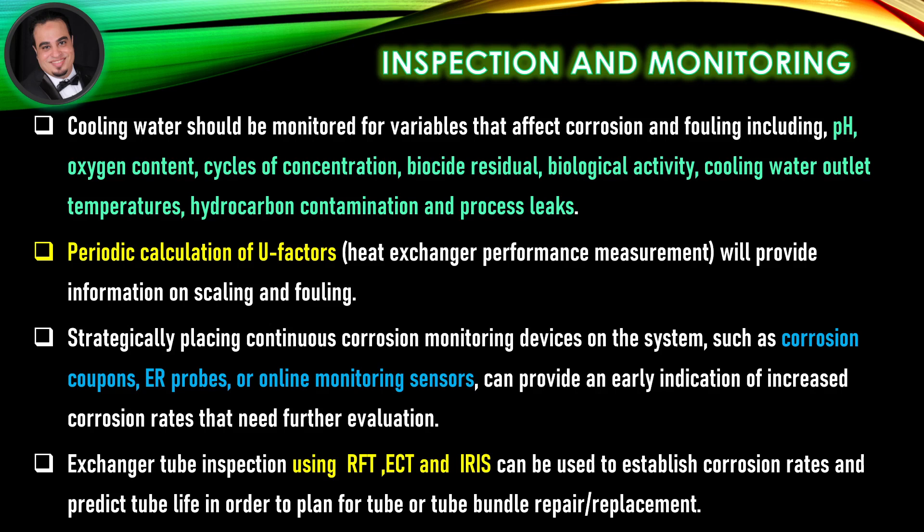Strategically placing continuous corrosion monitoring devices on the system — such as corrosion coupons, ER probes, or online monitoring sensors — can provide an early indication of increased corrosion rates that need further evaluation. Exchanger tube inspection using Remote Field Testing, Eddy Current Testing and Internal Rotary Inspection System can be used to establish corrosion rates and predict tube life, in order to plan for tube or tube bundle repair or replacement.